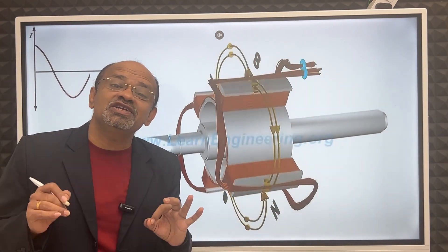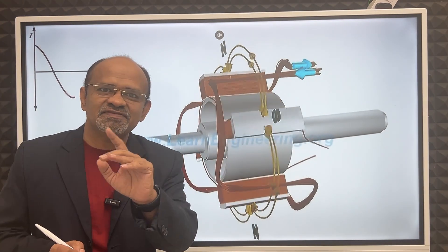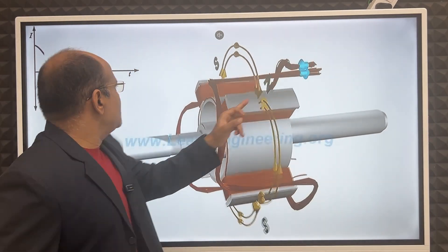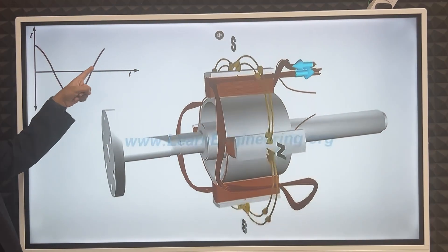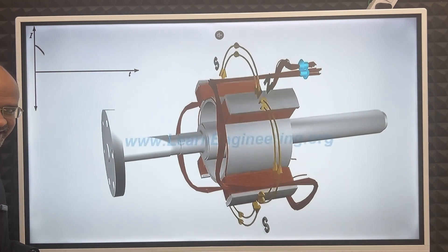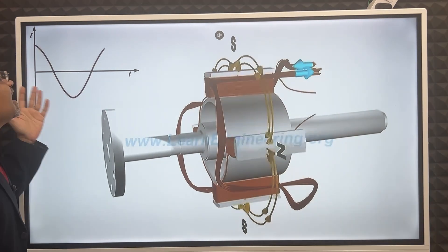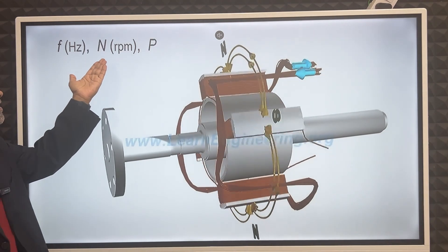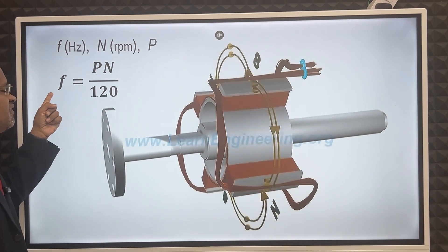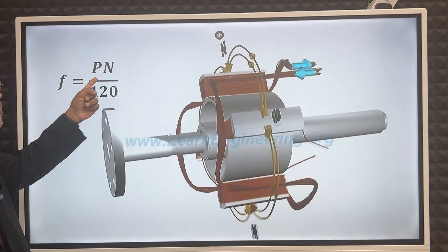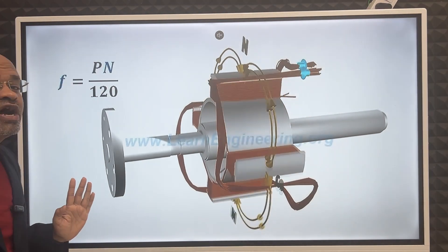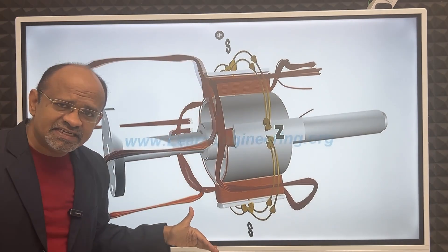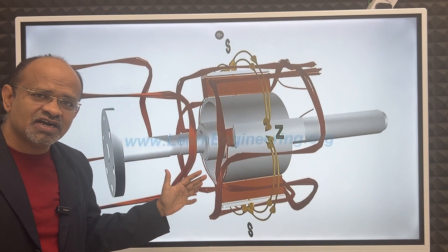The phase difference is 120 degrees — 360 divided by 3 is 120. In one coil, we get power this way. The frequency formula is: f = pn / 120. Whether you want to produce electricity at 60 Hz or 50 Hz, this formula applies, where p is the number of poles and n is the RPM.